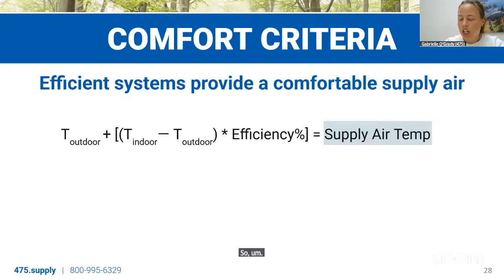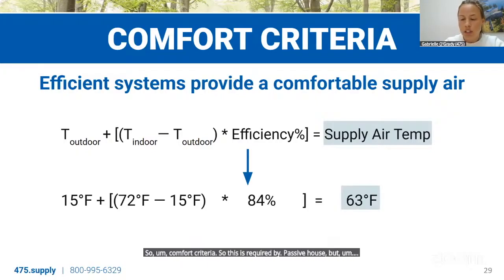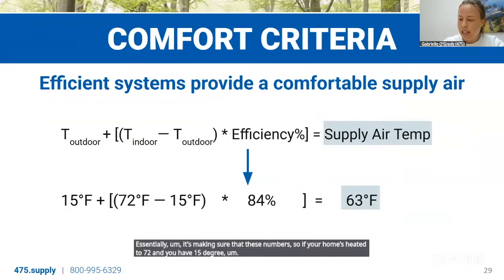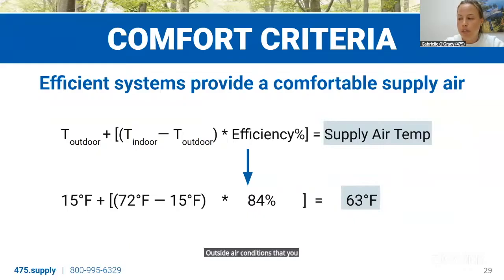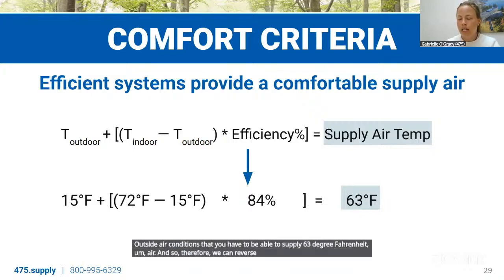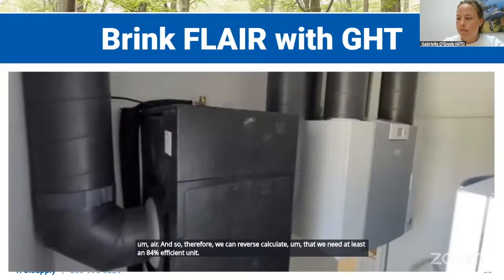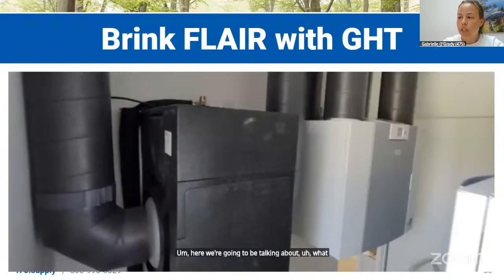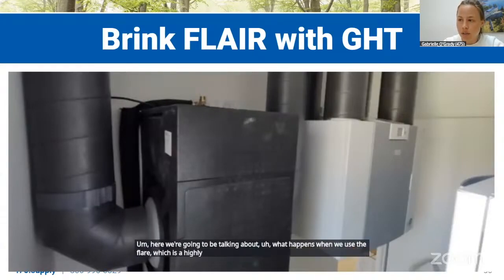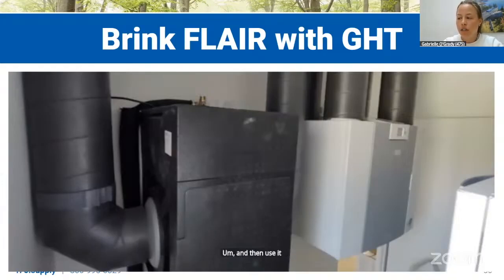So, comfort criteria. This is required by Passive House, but essentially it's making sure that if your home's heated to 72 and you have 15-degree outside air conditions, you have to be able to supply 63-degree Fahrenheit air. Therefore we can reverse calculate that we need at least an 84% efficient unit. Here we're going to talk about what happens when we use the FLAIR, which is a highly efficient unit, in combination with the GHT geothermal preconditioning system.